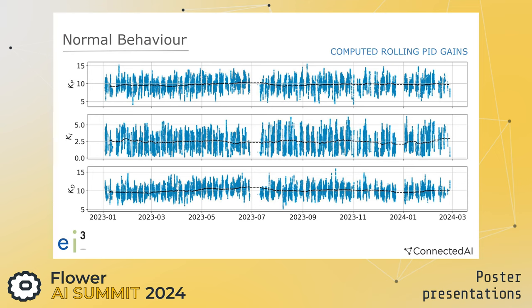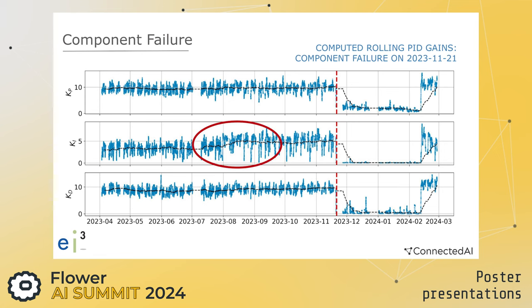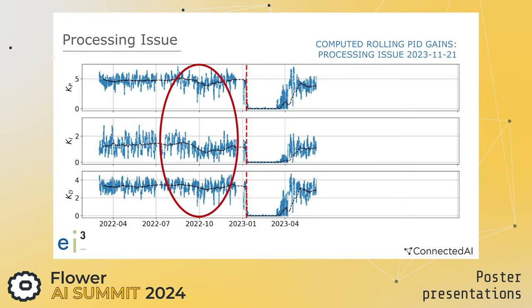There are, however, some components detected through this anomaly approach where we see an increase of the integral gain followed by all gains dropping drastically — and when we analyzed that, we realized the component had actually failed. We also observed another behavior where all gains start to behave very erratically, which corresponded to a processing issue. This is a perfect example of how through this analysis we are able to detect processing issues, not just for the component that the PID is directly controlling. Applying this analysis to a large scale of real-world data made us confident this can be an essential future approach for predictive maintenance.